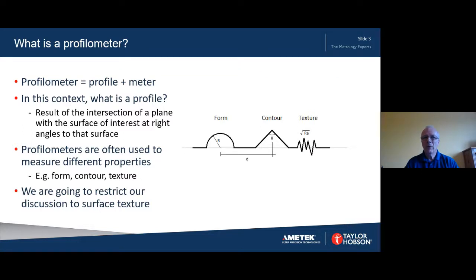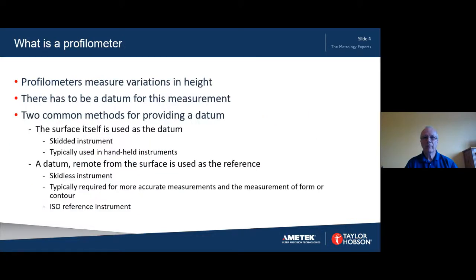For the purposes of this presentation I'm going to restrict the scope to surface texture and more specifically I'll be thinking about surface roughness. So a profilometer works by measuring variations in height from a datum. There are two classes of stylus profilometer based on how that datum is implemented. These classes of instruments are referred to as skidded or skidless.